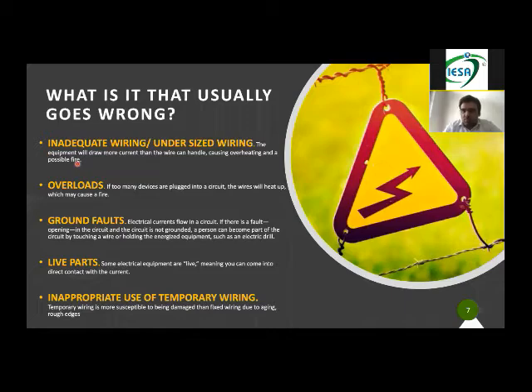Second most common are overloads. Again, if there are no safety devices present to shut down the electricity, there is a certain capacity house power can give you. Maybe if you're taking 100 kilowatts, the wiring also has to be laid according to 100 kilowatts. If you're trying to put more on the wire, 150 kilowatts or more load, ultimately that will also result in fire on site.